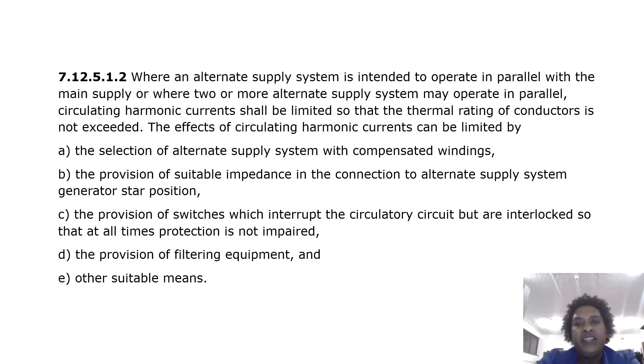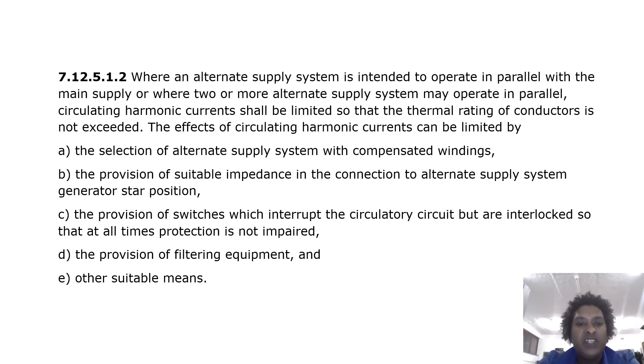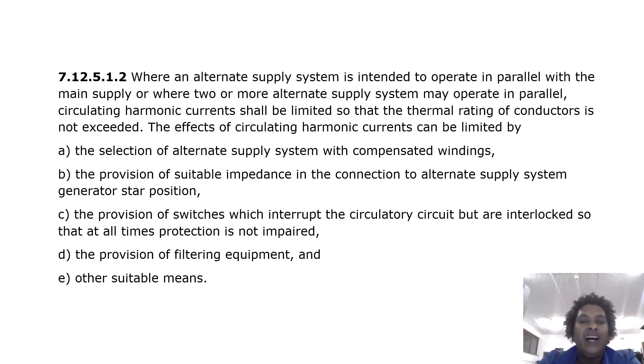Where an alternate supply system is intended to operate in parallel with the main supply, or where two or more alternate supply systems may operate in parallel, circulating harmonic currents shall be limited so that the thermal rating of conductors is not exceeded. The effects can be limited by: selection of alternate supply systems with compensated windings; provision of suitable impedance in the connection to the alternate supply system at the generator star point; provision of switches which interrupt the circulatory circuit but are interlocked so that protection is not impaired; and provision of filtering equipment and other suitable means.